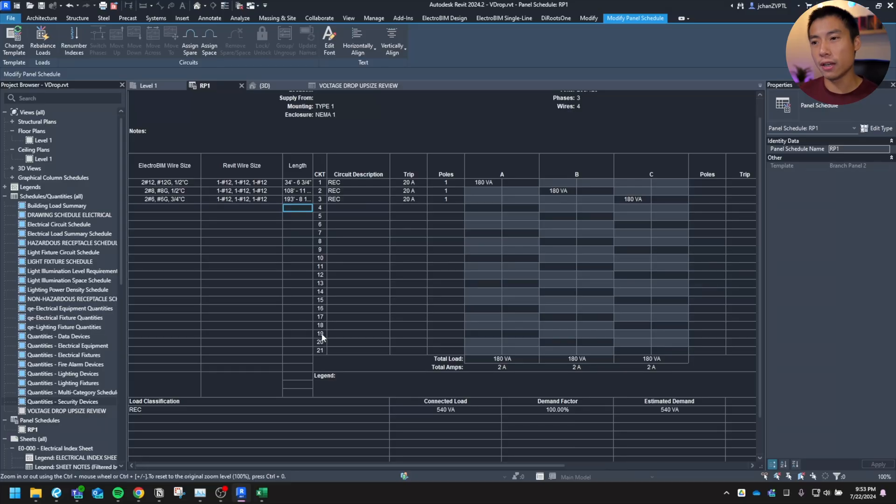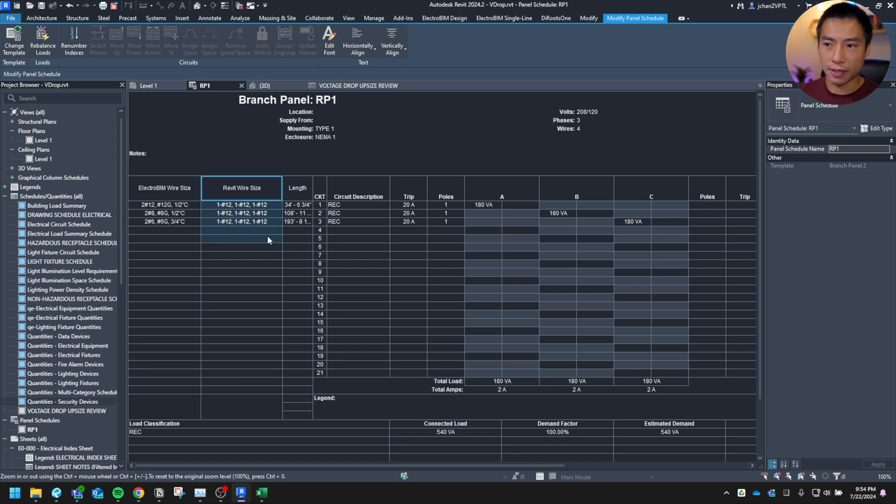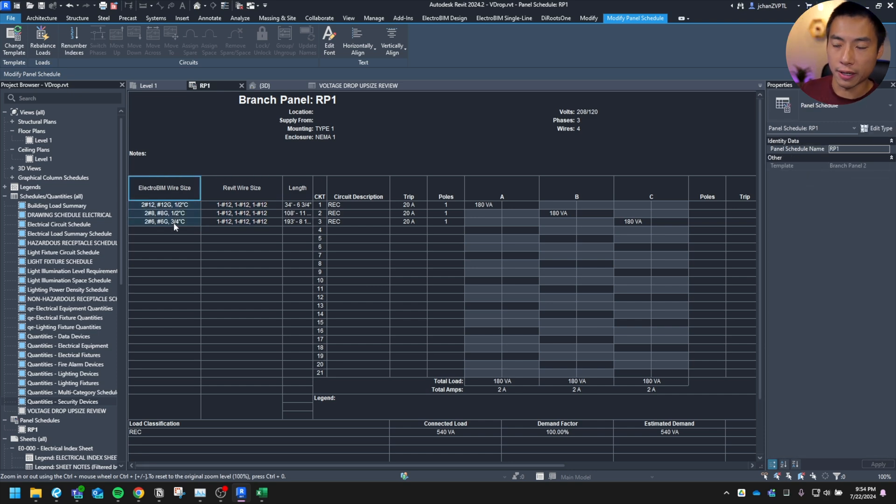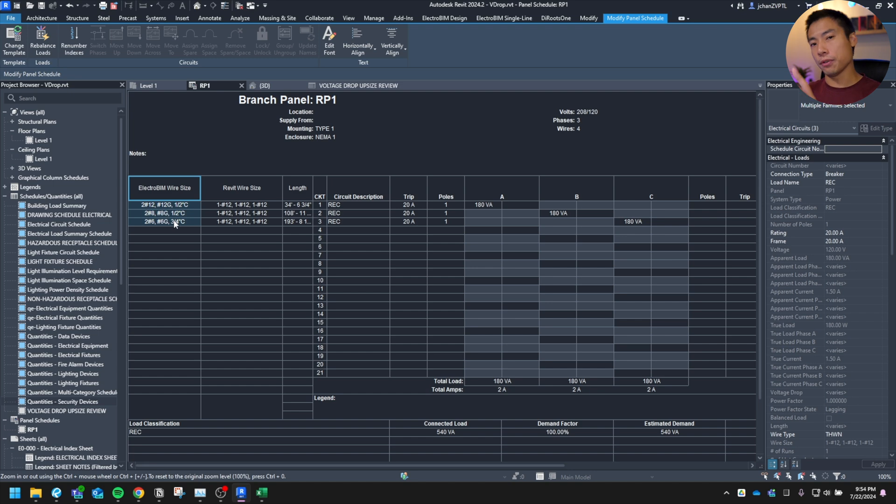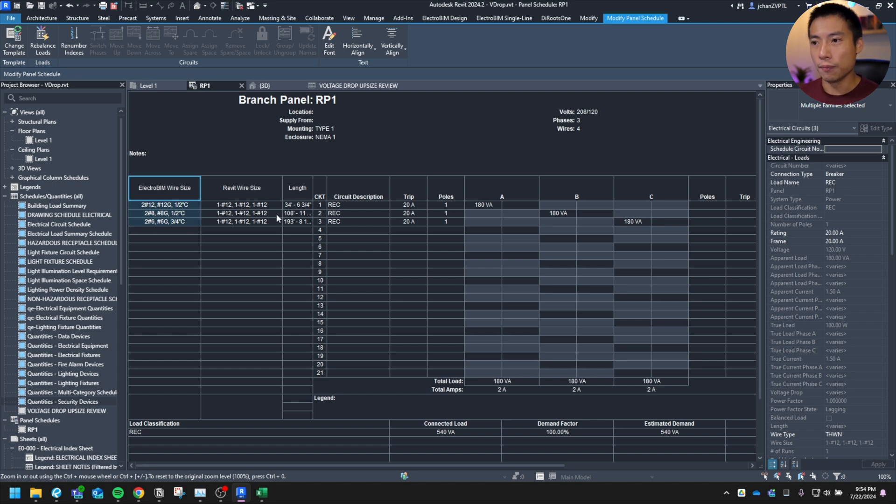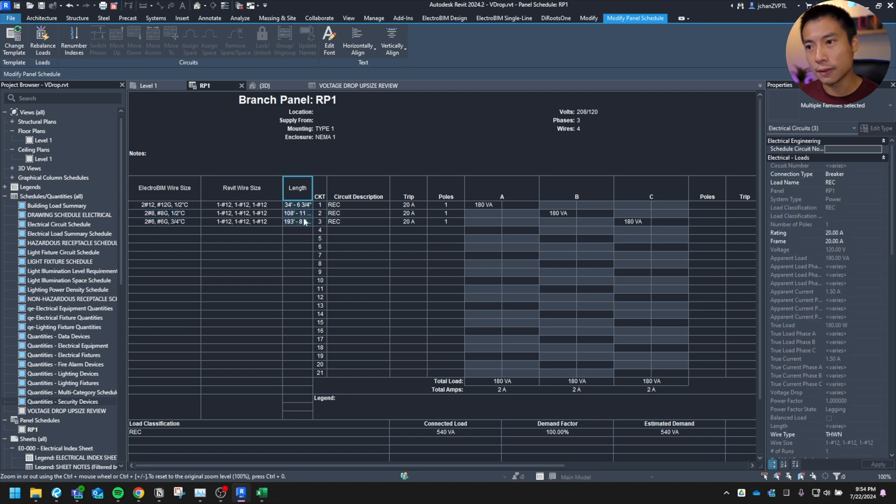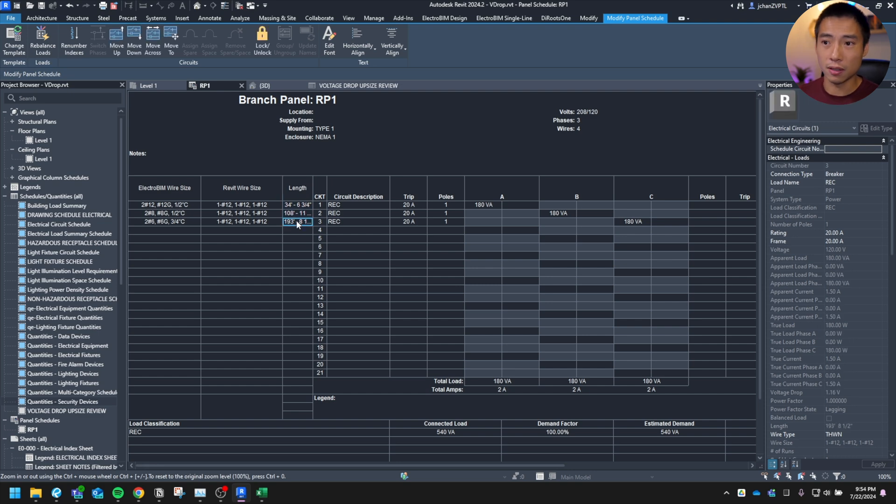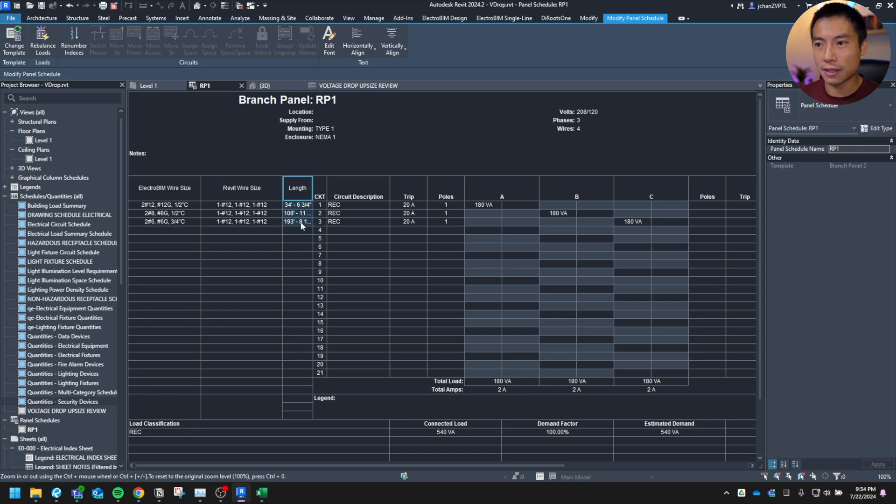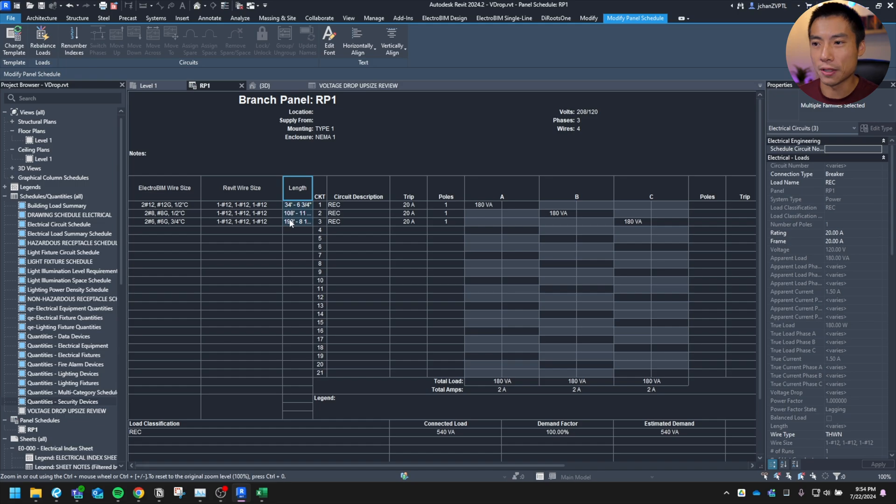You can see here, the panel schedule I have kind of cobbled together, has the Revit wire size as Revit would have done it. And it has the ElectroBIM wire size with the 80% calculation box checked. And honestly, I probably would keep the ElectroBIM wire size. The length is here just to prove my point saying that it's a significant distance, which would justify your larger branch circuiting. Sometimes it's nice to have it. I know some firms put them in some firms don't, but it's up to you.